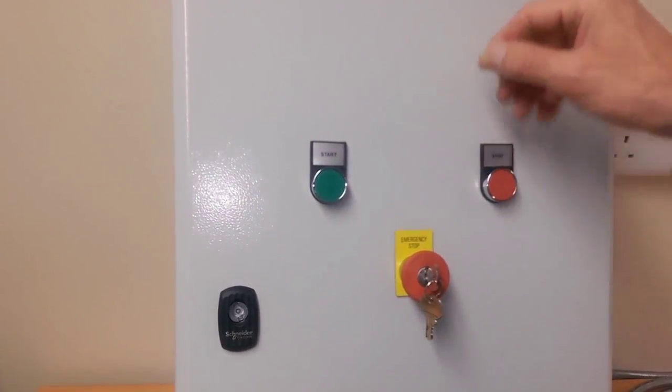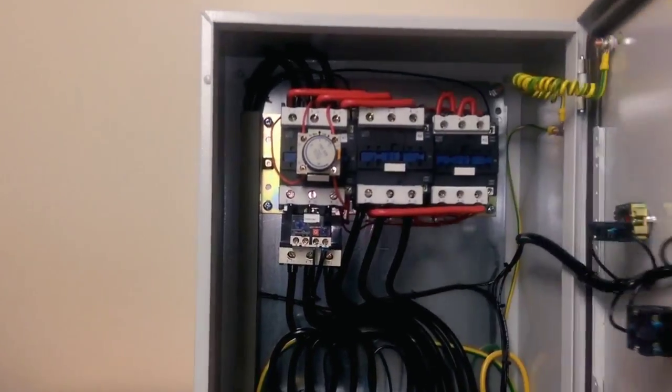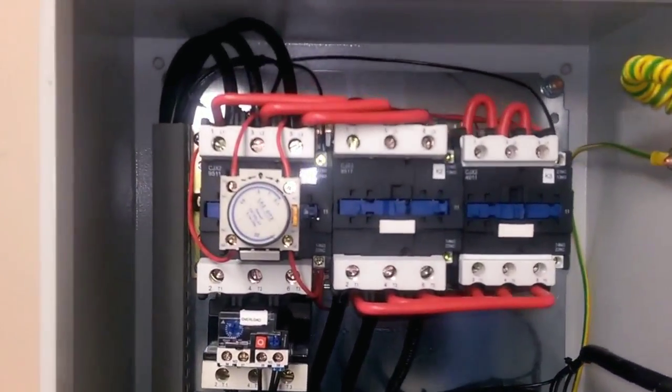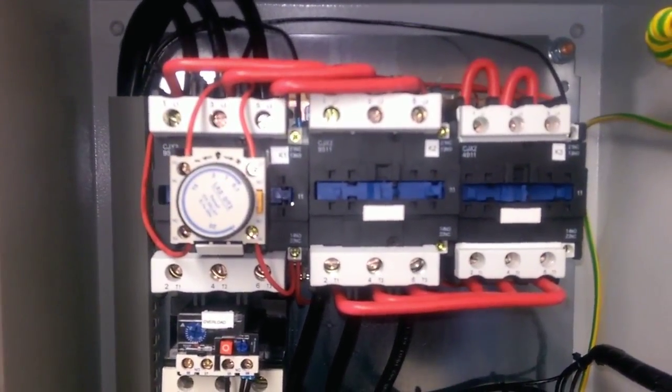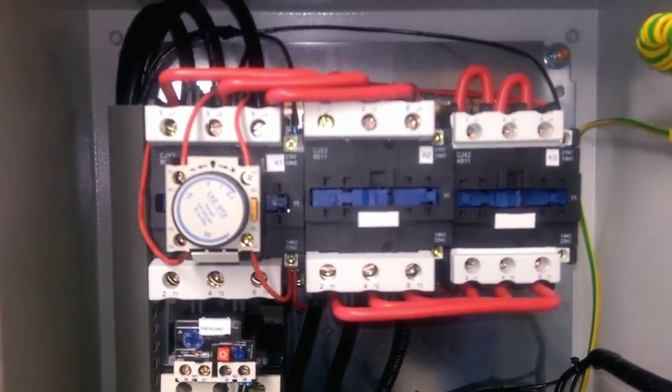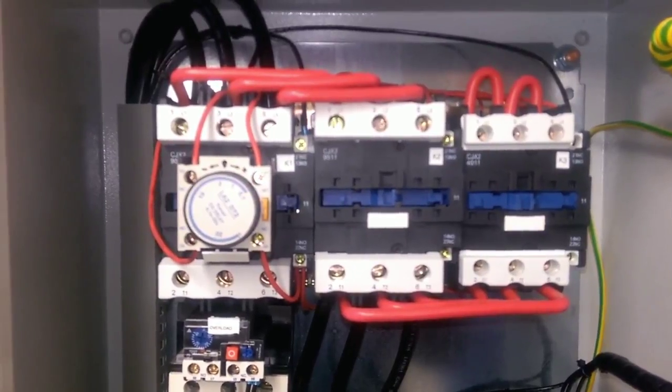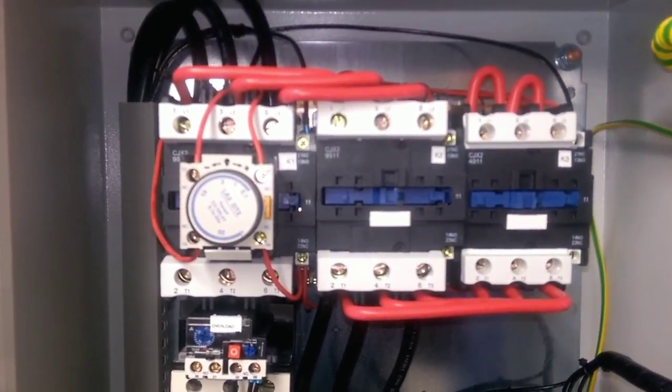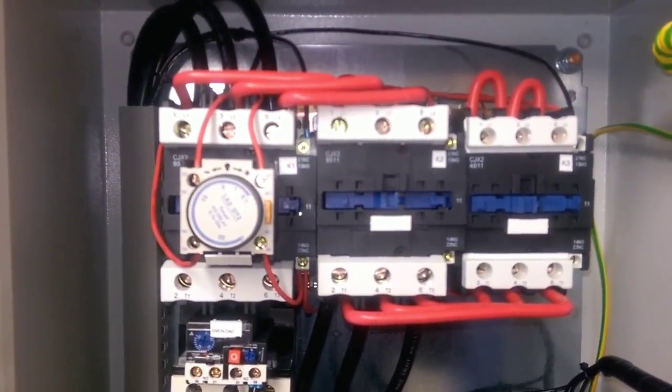Okay, I'll just show you this from inside the panel. If I press the start button, you can see the star and main contactor pulling in, then the timer initiates the changeover, and the delta and main contactor pulling in.